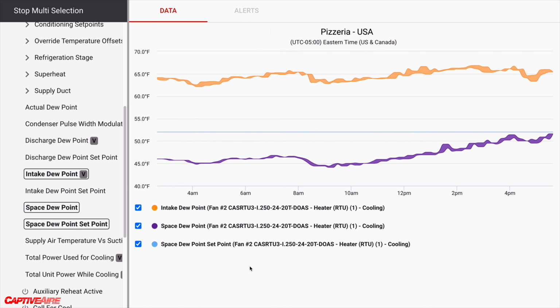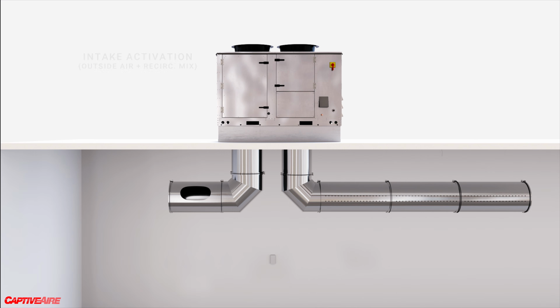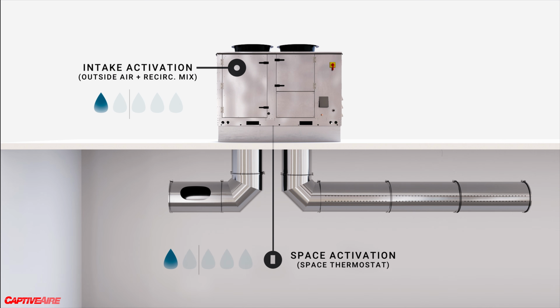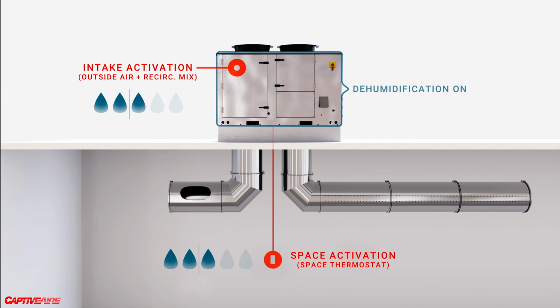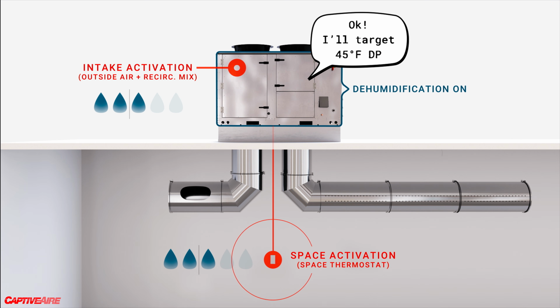But essentially what's going on here is this unit was set up by default with a more simplistic dehumidification logic approach. It was saying, all right, if your dew point goes above this value on the space side or on the intake side, we activate our dehumidification logic. But at the most simplistic design, that unit is just going to say, all right, anytime there's a dehumidification call, I'm hitting X dew point off of my coil. And usually if that's how the system is set up, which is very common for dedicated outdoor air equipment, it's going to shoot for whatever the worst case coil temp it needs, the lowest dew point it would need to cover itself on the most humid days.